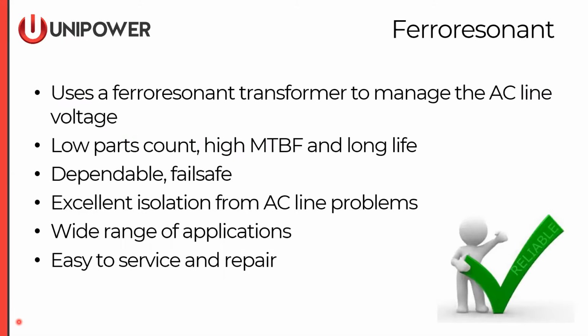A Ferro Resonant achieves its line regulation more through physics and less through electronics. It uses a very, very large transformer and a tuning tank circuit to regulate the DC output. What that means is there's not a lot of electronic parts inside the Ferro Resonant unit. So it's very reliable, a very tried and true design, and a low parts count leads to a higher MTBF. They're very dependable. We've had these units out for 20, 25, 30 years or more. It covers a wide range of applications, and we'll talk about that on a chart later when we show the voltages and outputs. And they're very easy to service and repair.